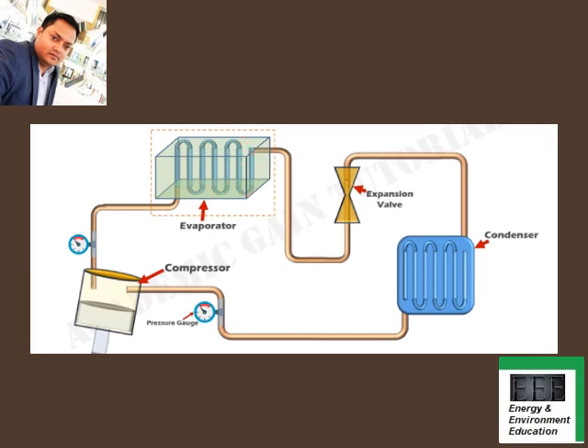The main purpose is to ensure a continuous cooling effect in the evaporator. The evaporator is placed in the region where we need cooling; it absorbs all the heat of that region and passes that heat to the cold refrigerant passing through the evaporator coils, thus cooling the surrounding environment. The compressor pressurizes or compresses the vapor refrigerant inside the compressor chamber. Commonly, either ammonia or freon is used as the heat-carrying medium.